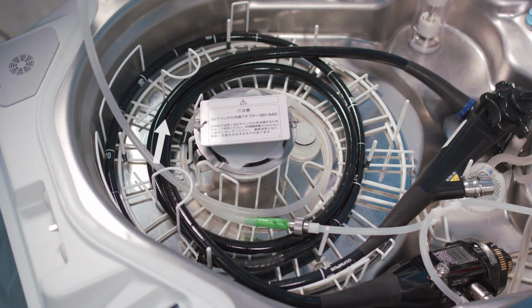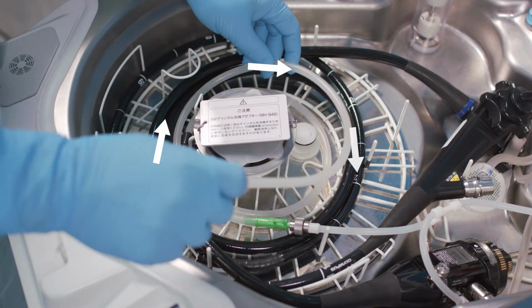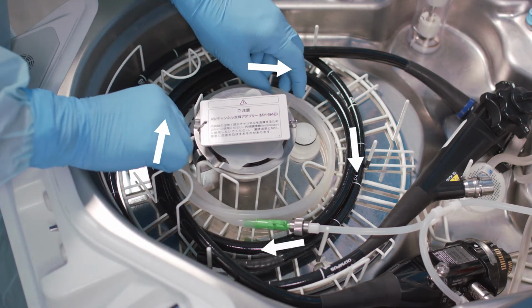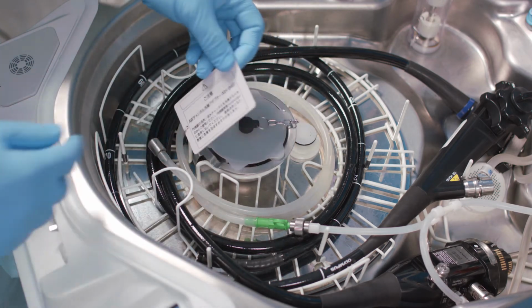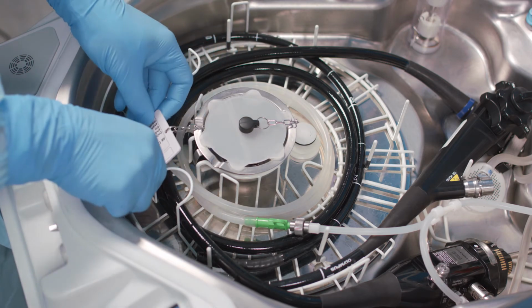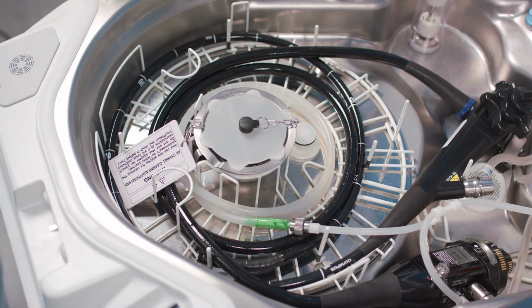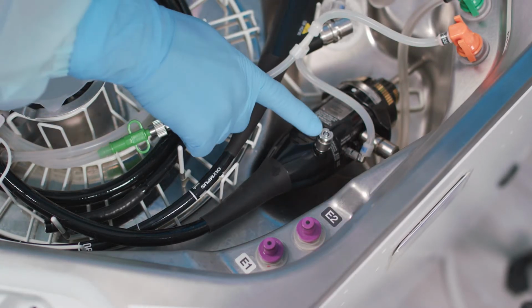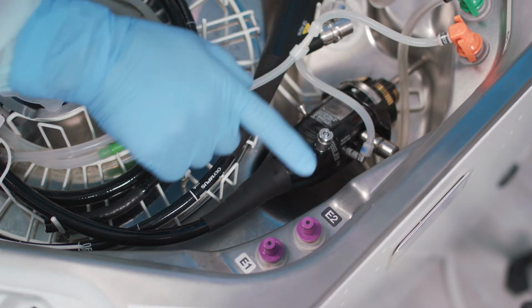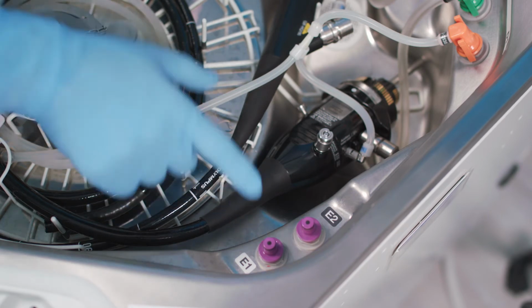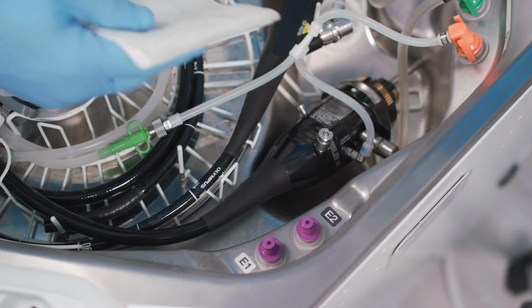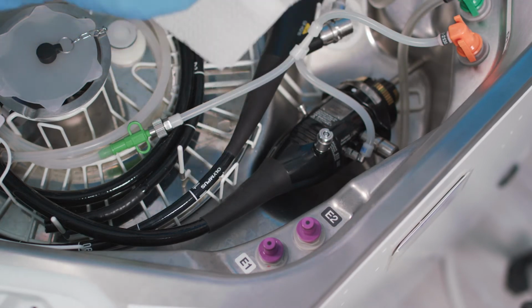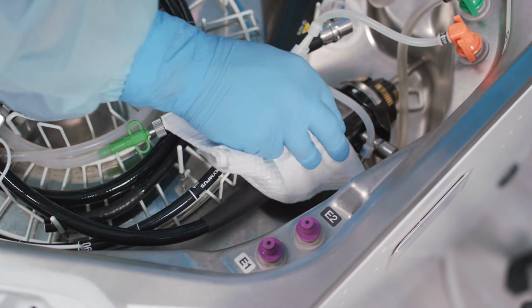Now, we're going to wrap the auxiliary water tube clockwise in the inner area from the universal cord. After setting the auxiliary water tube, place the indicator plate in its original position in the basin. If the venting connector of the endoscope or the equipment side leak test connector is wet, wipe it thoroughly with a clean cloth moistened with alcohol.